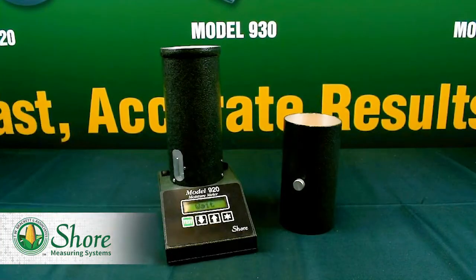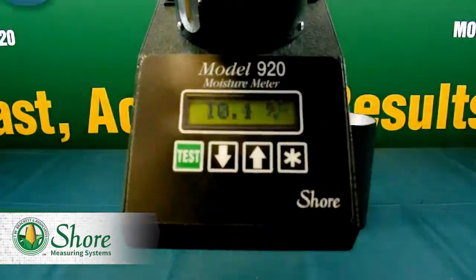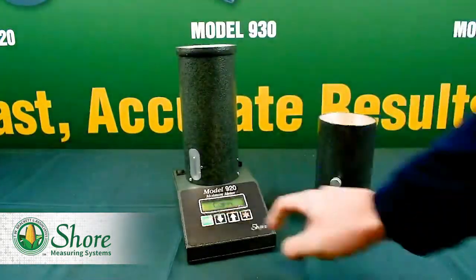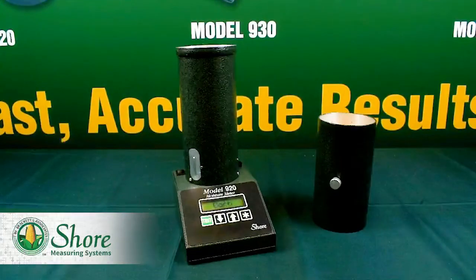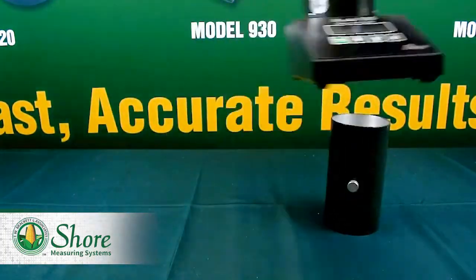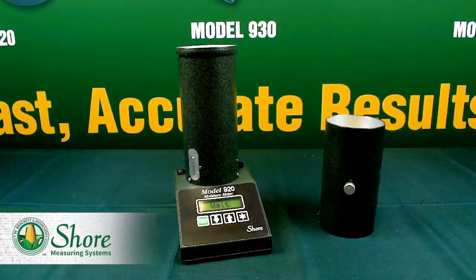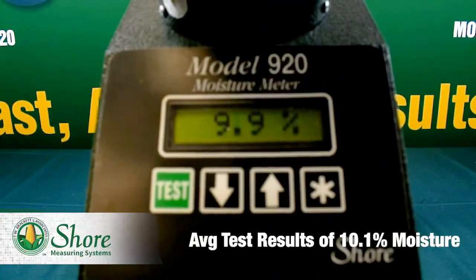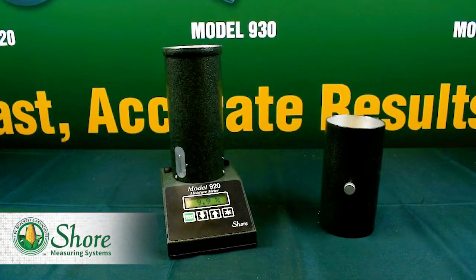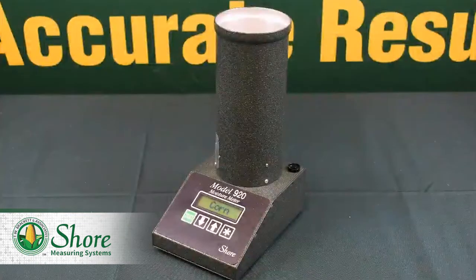Lastly, we'll see how the Shore 920 compares to the SL95. For the three uninterrupted runs on the 920, we got 10.1, 10.2, and 9.9, which comes out to an average of about 10.1 — which is, unsurprisingly, exactly what we got for the SL95. Keep in mind that the SL95 is a certified lab unit, which means that the 920 lines up perfectly with the same type of unit that would be used in a grain elevator.